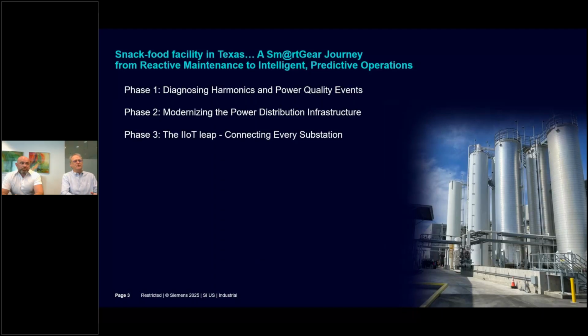Phase 3 was, as we saw we were able to start hardening some loads, we wanted to look at whether we could do it for the whole facility. The facility had about 12 substations, and a lot of those weren't Siemens - all of them except the new one were not Siemens. So how did we connect all that into the Smart Gear?